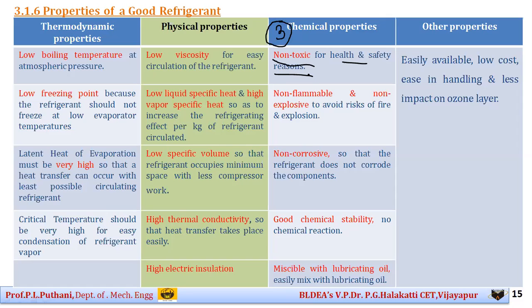The refrigerant should be non-flammable and non-explosive. When there is a sudden leakage and the refrigerator is running on electricity, if the refrigerant contacts electricity and is highly flammable, it may catch fire or lead to an explosion. To avoid risks of fire and explosion, prefer non-flammable and non-explosive refrigerants. Also, since the refrigerant flows continuously through all parts — evaporator, compressor, condenser, throttle valve — for many years, parts may corrode. So the refrigerant should be non-corrosive so that components do not undergo corrosion.